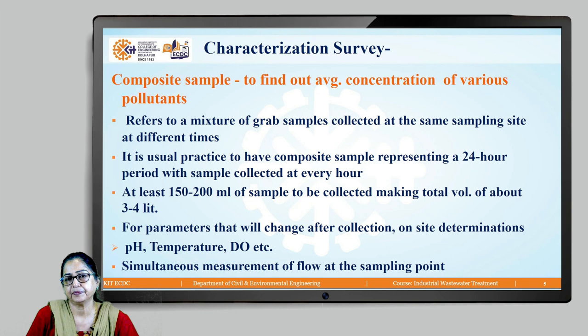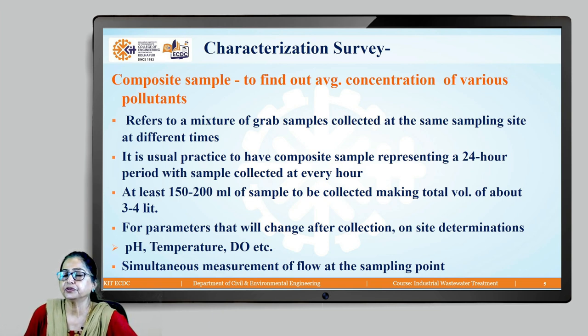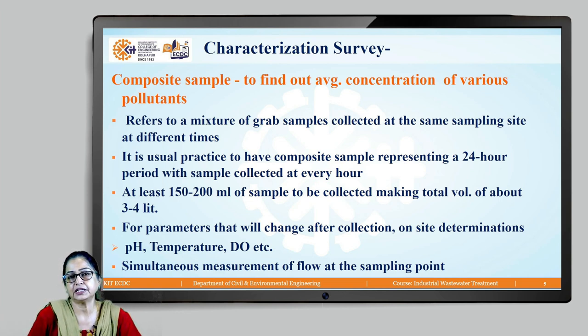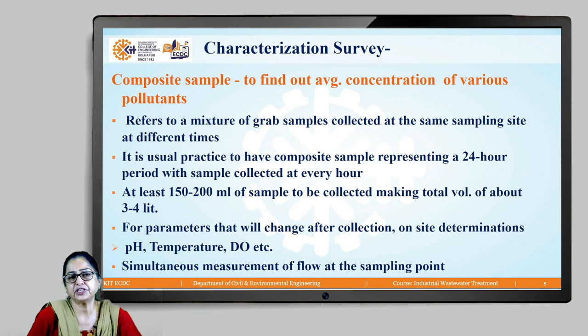At a time, 150 to 200 ml of sample is collected and transferred into a large container with total volume 3 to 4 litres at the end of the 24-hour period. Once the sampling duration is over, you have a mixture of samples collected over the time period. Then you mix the sample thoroughly. Parameters which change with time — that is pH, temperature, and dissolved oxygen — are to be determined on site.